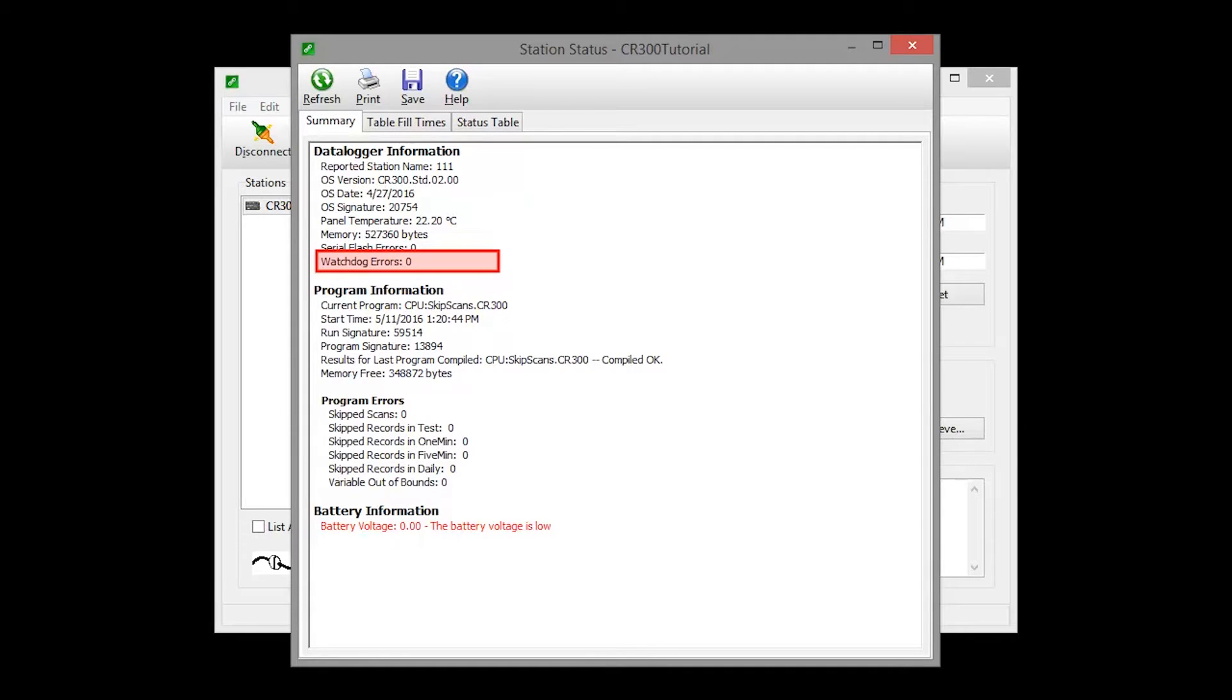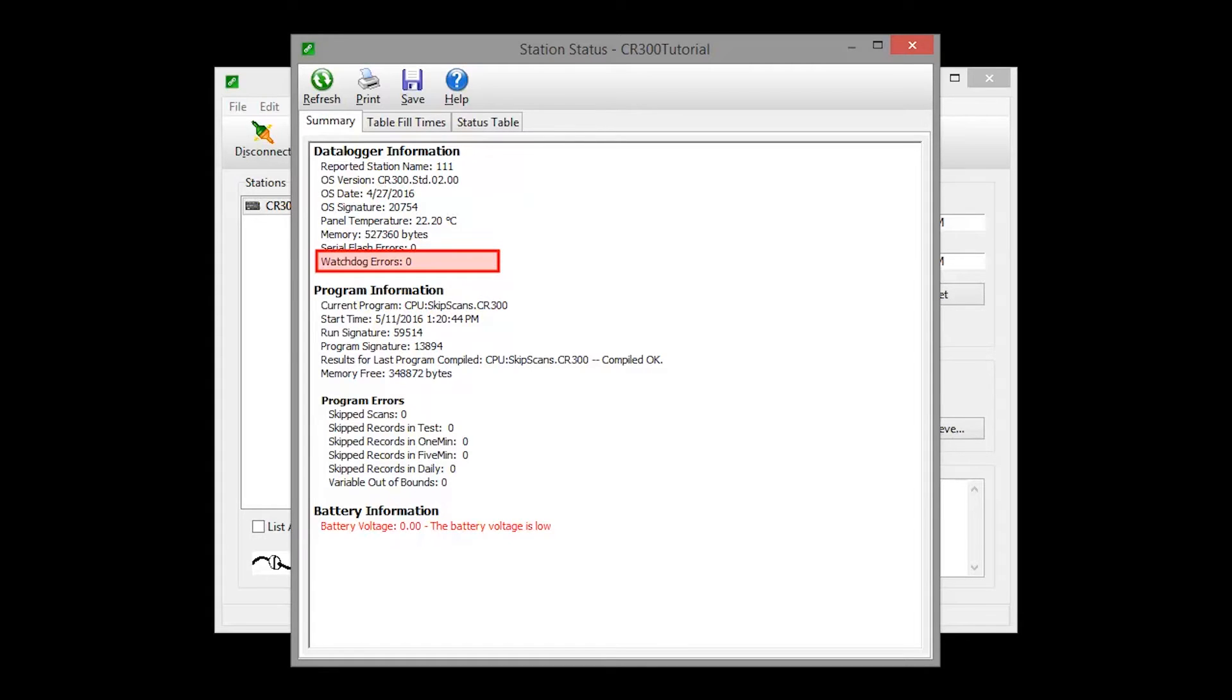Watchdog errors indicate that the data logger has crashed and reset itself. A few watchdogs indicate that the data logger is working as designed and are not a concern. The most common causes of watchdog errors are power supply and transient voltage issues. These problems should be corrected and the watchdog counter reset.